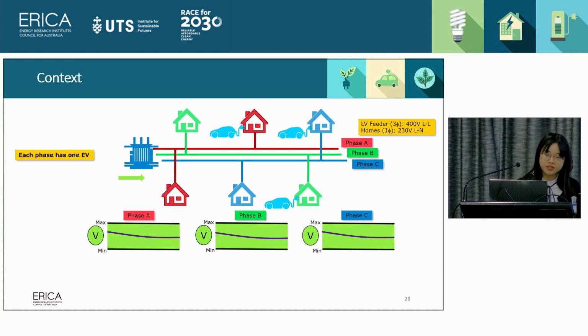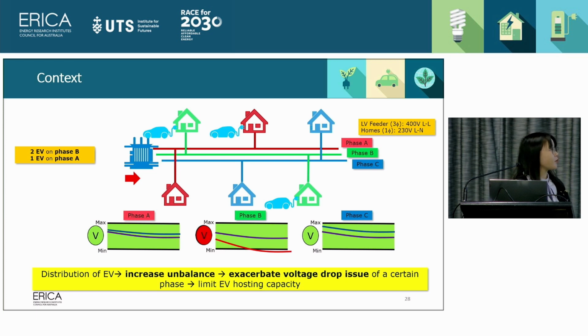So here is a simple feeder. Each phase has two customers, and one of them has an EV. So the voltage along the feeder is the same among the three phases, and it drops a little bit from the head to the end of the feeder. If we have two EVs on phase B and only one on phase A, there are still three EVs, but two of them are on phase B. So the voltage along phase B will be much lower, and it may reach the lower limit. So the distribution of EVs may increase unbalance and exacerbate the voltage drop issue of a certain phase. Here it is phase B, and it may limit EV hosting capacity.